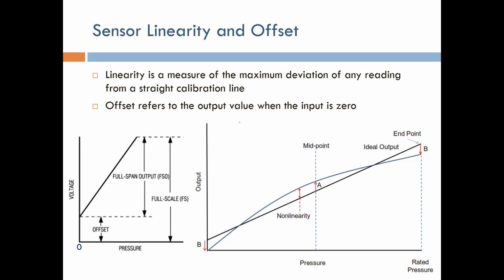One example is measuring oxygenation level in the blood. The output measures the concentration of oxyhemoglobin relative to deoxyhemoglobin. When you measure that, you get results with really high nonlinearity. So what you do is program the curve that relates that nonlinear quantity to the output you want, and you don't have to linearize it in this case.